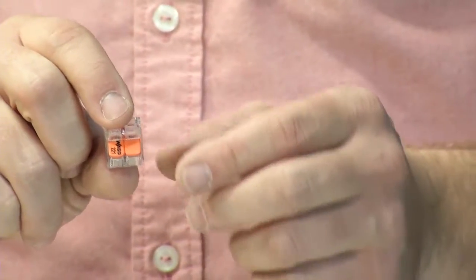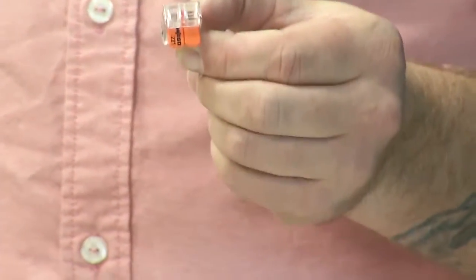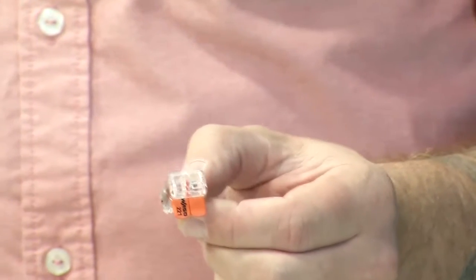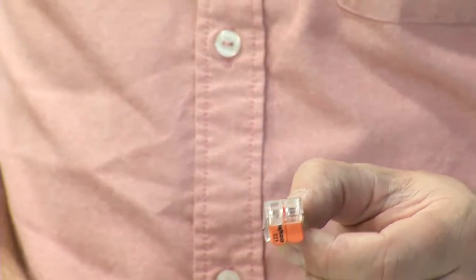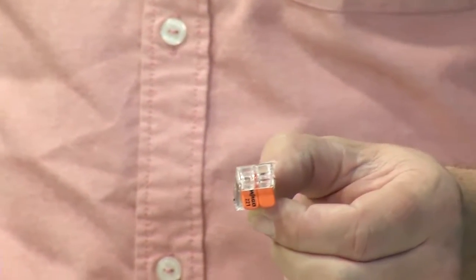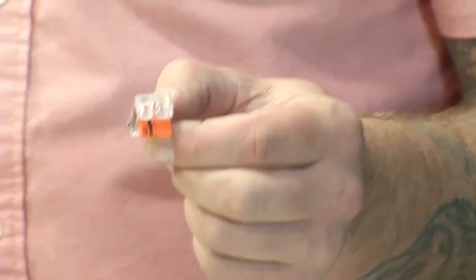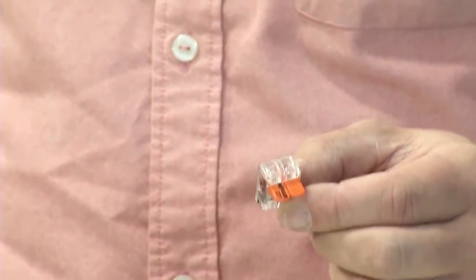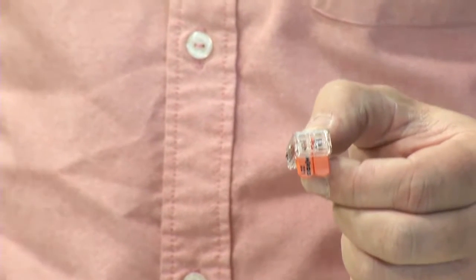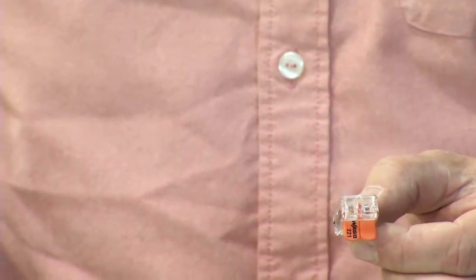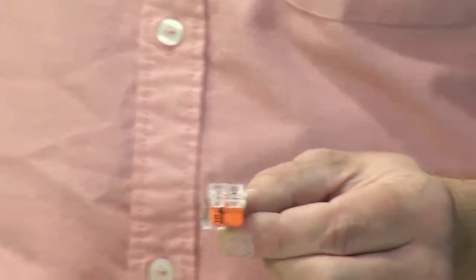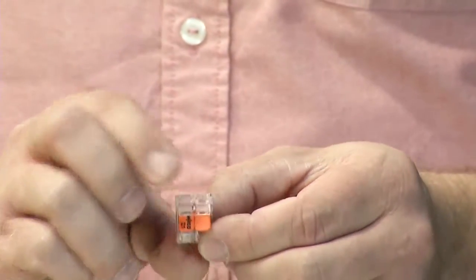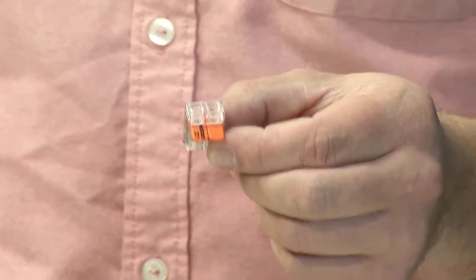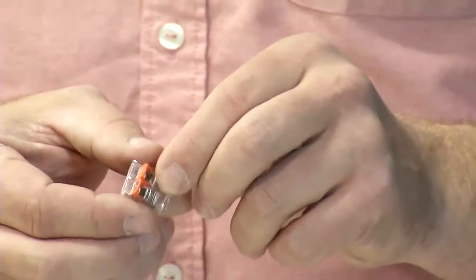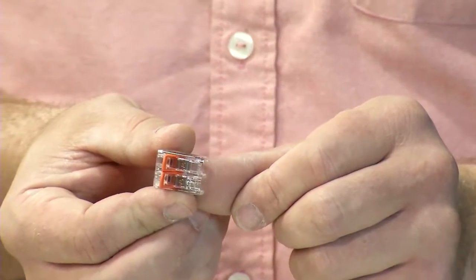There are some Chinese knockoffs, but WAGOs themselves are being used throughout the OEMs in our industry, getting away from bell connectors and little lock nuts. We are actually going to be using them as the standard in our transfer switches and on our power centers. It'll be an option—not on every power center, but on our DC fuse boards we're going to have WAGO connectors like this, so you're going to get away from the screw terminals.